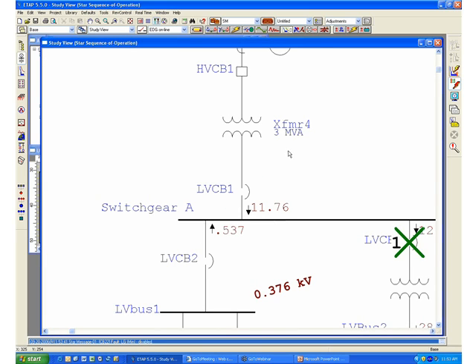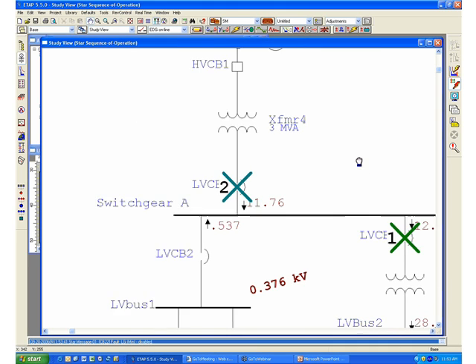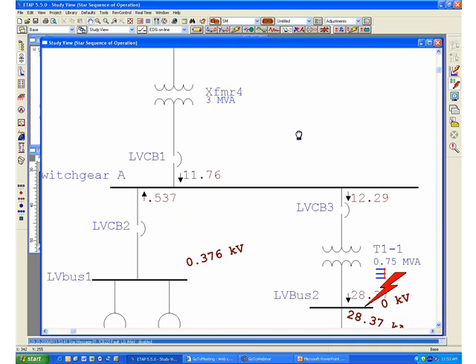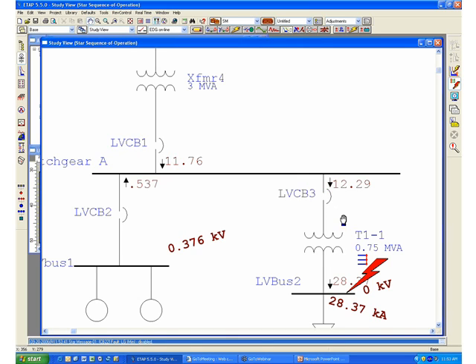you'll be able to see that the program automatically determines the order at which protected devices will operate. In this case, LVCB3 will be the one that would trip first, and then it will be followed by LVCB1.